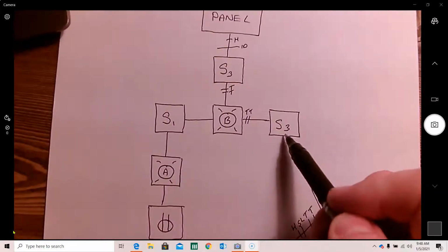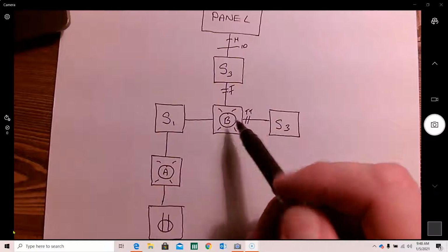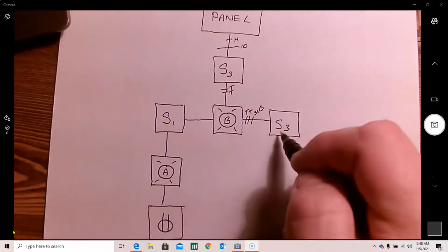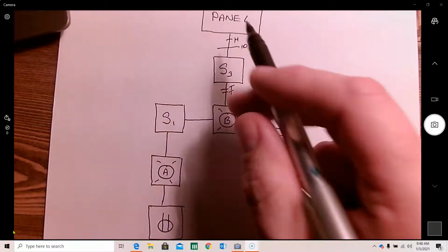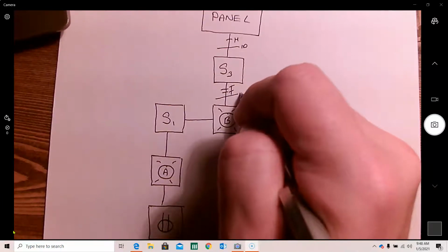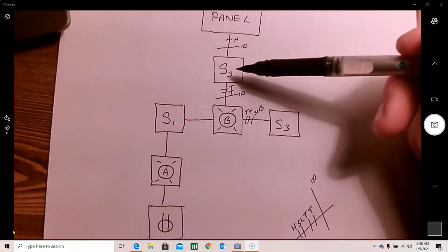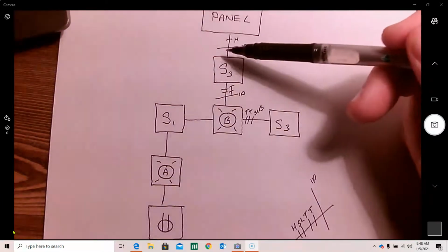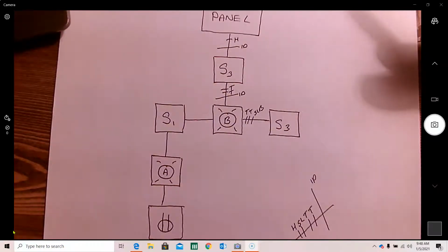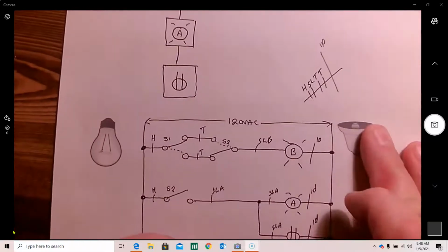So my second three-way switch going to light B, I'm going to have switch leg B coming out, going to my light, and then my light has an identified traveling back up to the source, my panel. Right, so I have an identified coming back to here. I already have an identified in this raceway here, so I don't need to add another one. Perfect. So that's the first line.